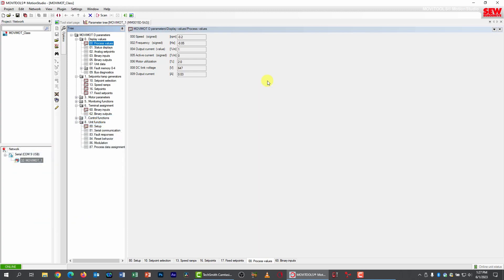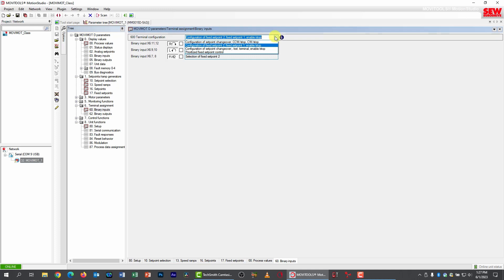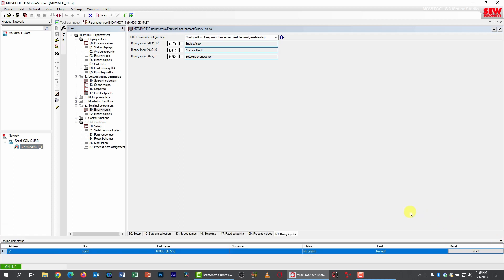I stop the drive and pick one of my other speeds. I turn on the counterclockwise switch to give binary number 01 — when I run the drive we get counterclockwise rotation at 500 RPM. I then change to binary 10 by turning counterclockwise off and F1/F2 on — now at 750 RPM counterclockwise, confirmed in the process values screen. Finally, I turn both counterclockwise and F1/F2 on for binary 11 — that brings us to 1,000 RPM. Four set points available. I stop the drive by removing enable.